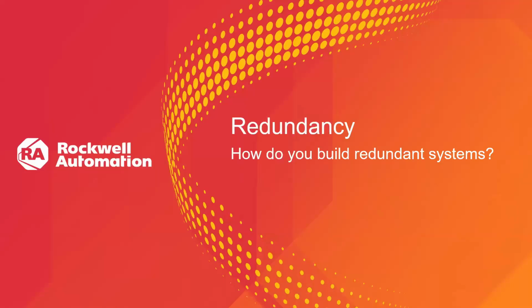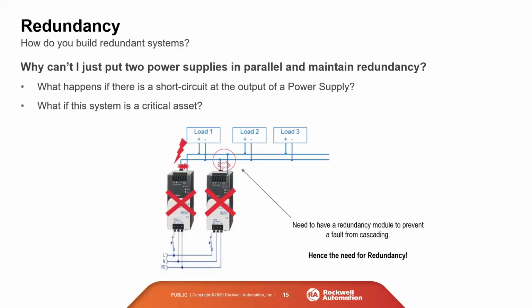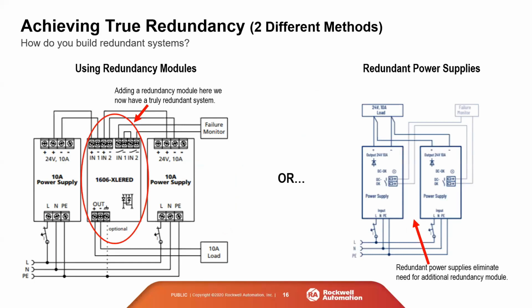So now that we know that we might need a redundant system, how do we build them? Why can't I just put 2 power supplies in parallel and maintain redundancy? Well, if there's a short circuit at one of the power supplies, because they're in parallel, there's a short circuit at the other power supply. So now you've lost 2 of your power supplies. So they have to be decoupled, and we do that with a redundancy module. So like I said, to solve that, you put in the redundancy module that decouples the load from the power supplies.